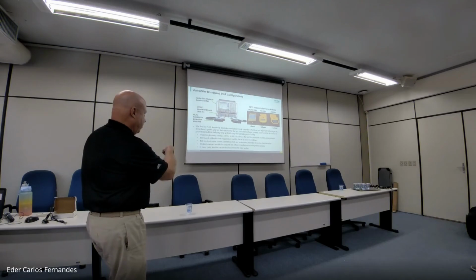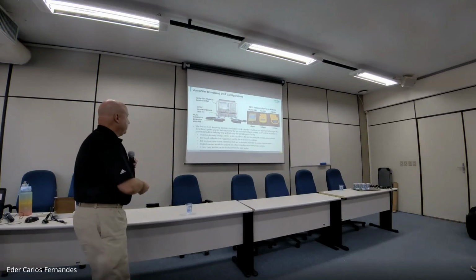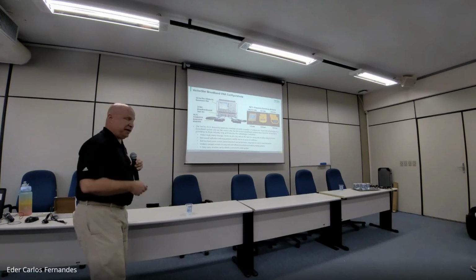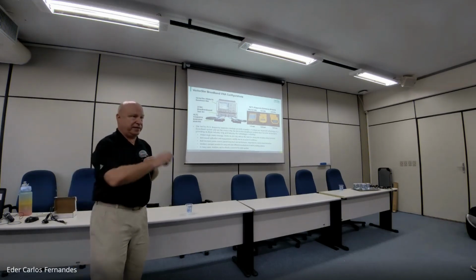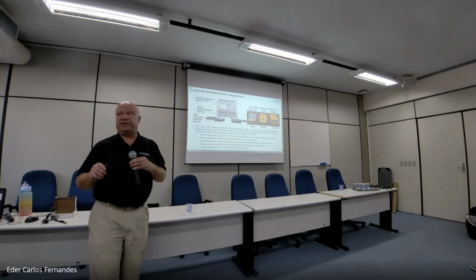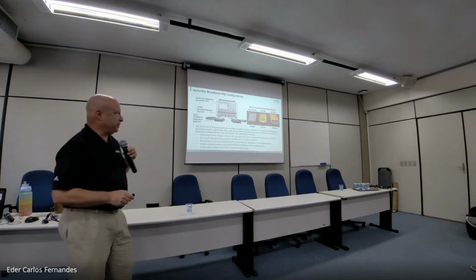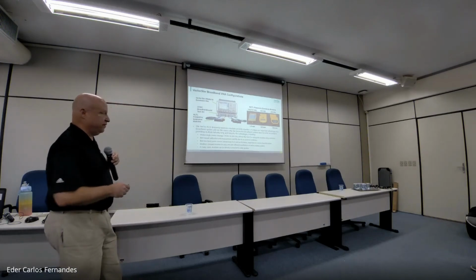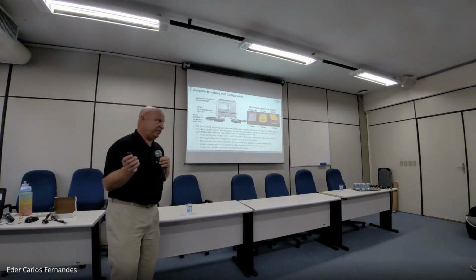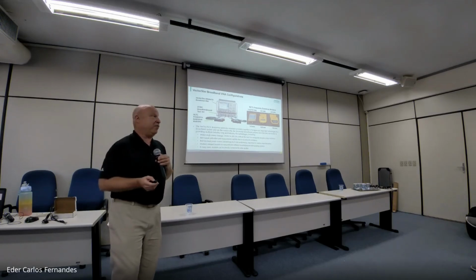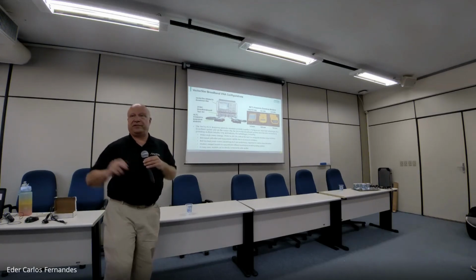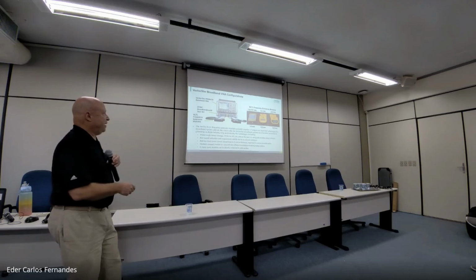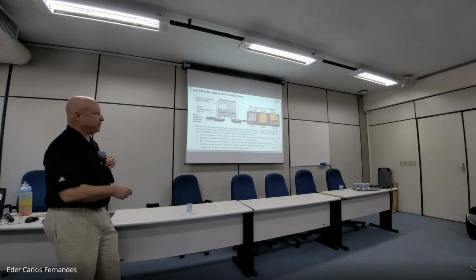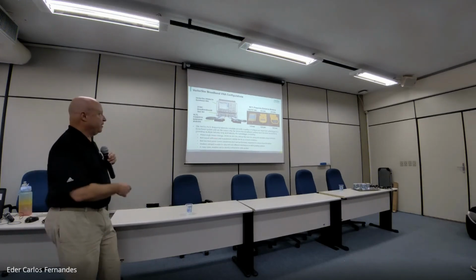Right, so basically all of these things apply. We have the single sweep coverage. We have the calibration stability, since we're not using anything external to the module. Everything's internal to the module. That helps us achieve better calibration stability over time and temperature. Very important if you're doing calibrations on wafer. Who wants to do calibration every hour? It's very complicated when you're on wafer. So again, having no external combiners like we used to have in the older generation systems would only add to more drift over time and temperature.